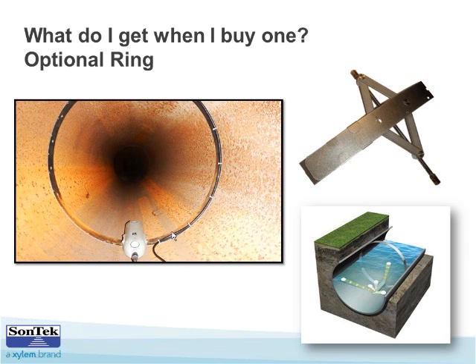Another thing I like about the design of the pipe ring here, it's a small thing, but here you see how the cable comes up, and it's very neatly zip-tied around the pipe, just to get it out of the way and make sure it's secure, because that is a critical thing that is sometimes overlooked, just making sure your cable is secure and not just flapping around there in the flow and getting stressed over time. And once it flexes one too many times, there can be intermittent problems that just turn into a nightmare. So a lot of stupid or big and small problems can be solved if you make your installation of the cable as well as the instrument clean.